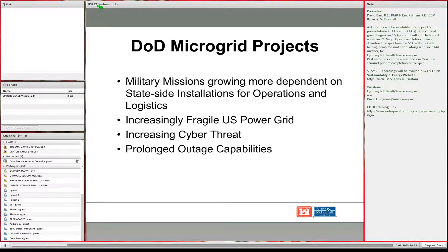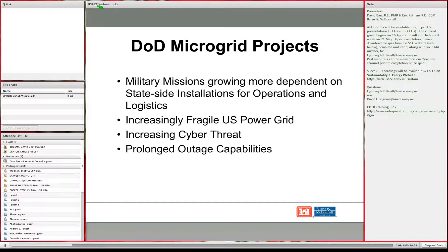Most diesel generators on buildings are installed with the assumption that utility power may be lost for an hour or up to eight hours, with fuel tanks sometimes sized for 72 hours. But a building critical in a four-hour outage remains critical after a four-week outage. After Hurricane Sandy, some Northeast installations were without power for up to two weeks—if those missions were supporting contingency operations overseas, that would have compromised national security.